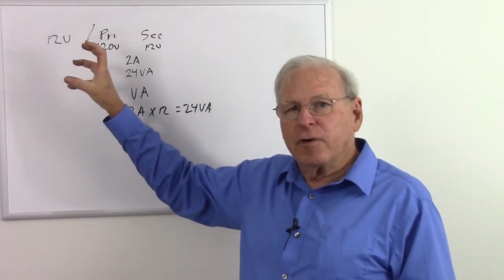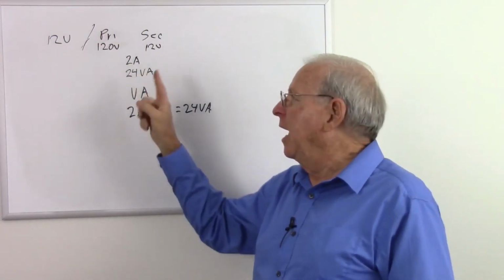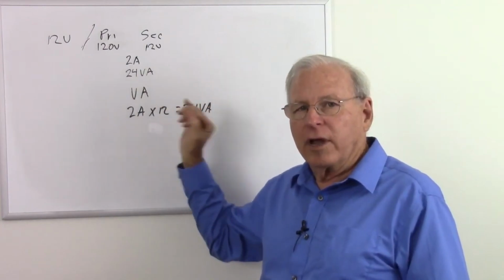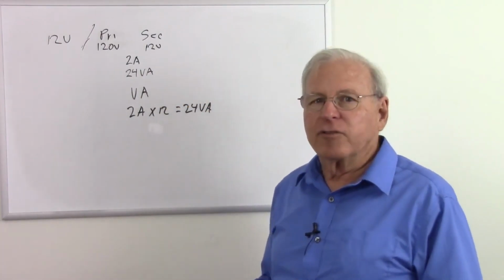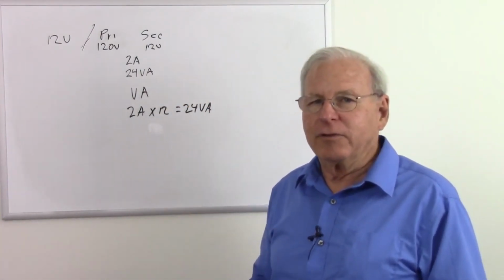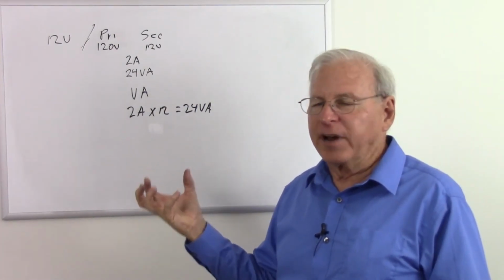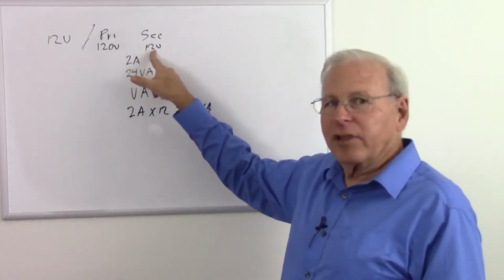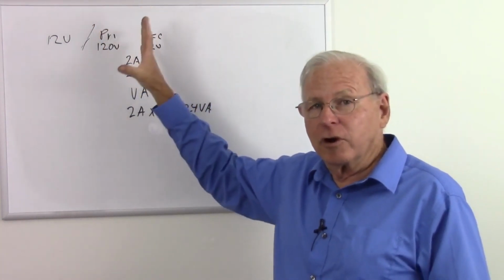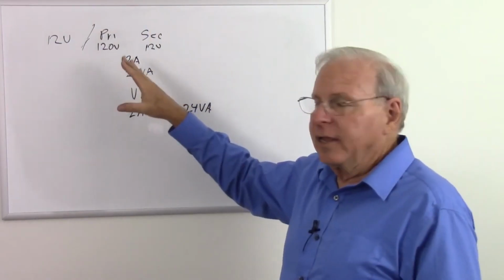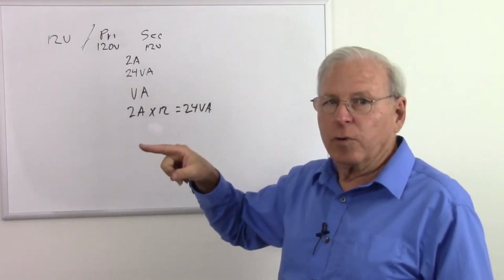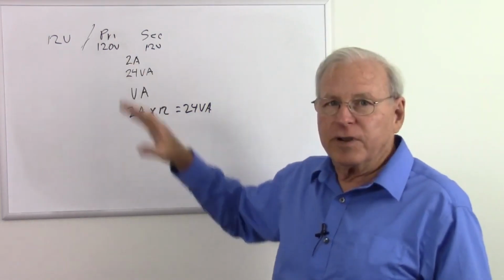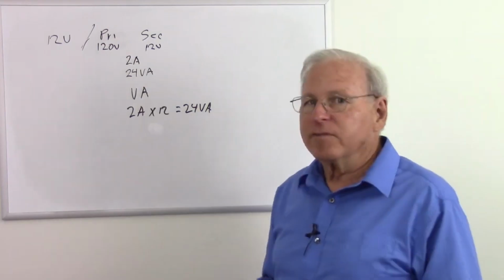So I have to use that formula to kind of figure out what my transformer is if it's specified in volt amps. So you're going to get a secondary voltage, possibly a primary voltage, and then either a secondary current or a number of volt amps, depending on the transformer you get. So you just have to, when you specify a transformer, how are they specifying it? As primary and secondary, or just secondary, in which case you have to assume the primary, depending on whether you're in Europe or North America. And in the number of amps, now the amps is easy, but they might specify it in volt amps, so you have to do a little math magic to figure out what your current is if they specify volt amps.